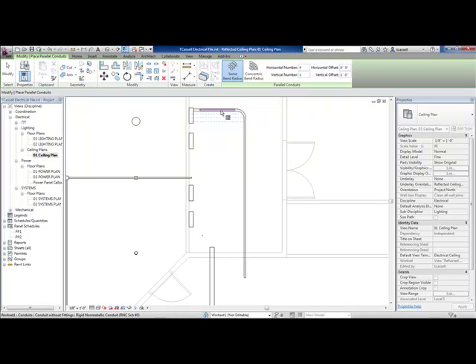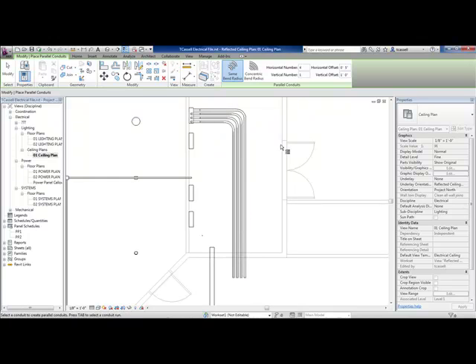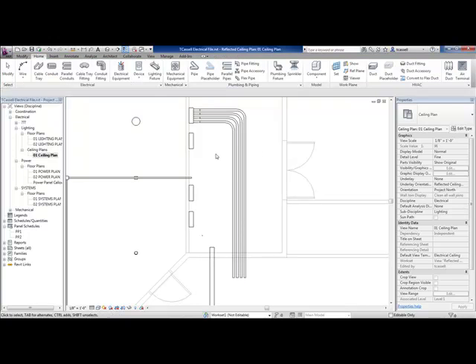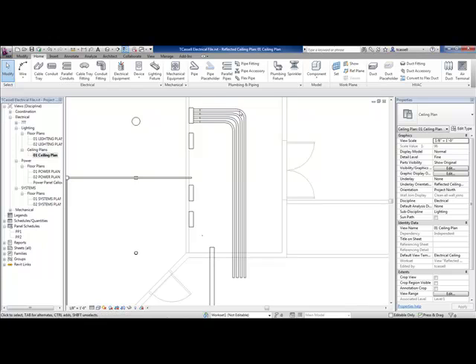One mistake I don't want anybody to make: when you hover over your first piece of Conduit and click, it's only going to create a parallel run of that one piece of Conduit. If you just press Tab, it'll create a parallel run for all the Conduits of that run. After the Conduit Run has been created, each one of these Conduits is independent.